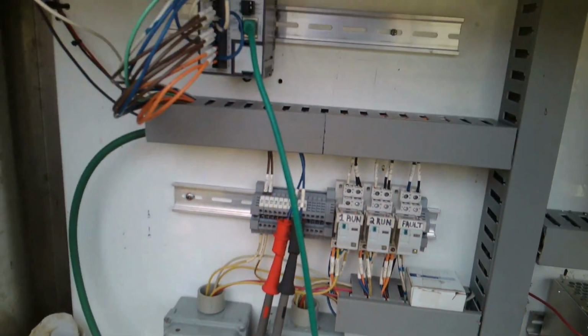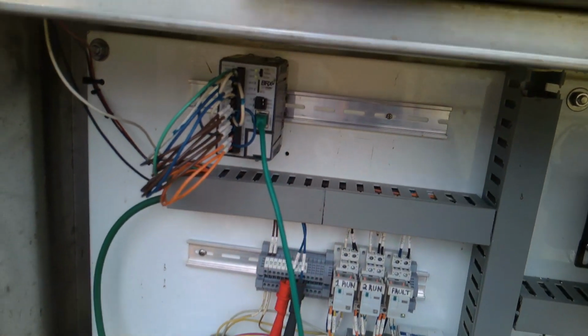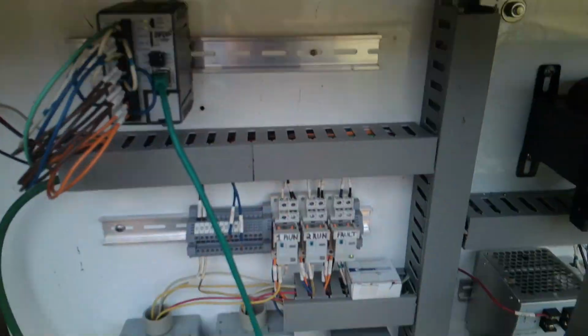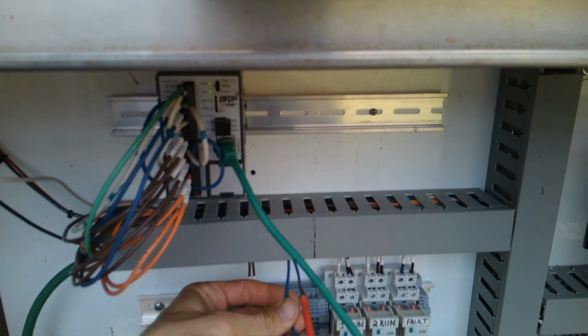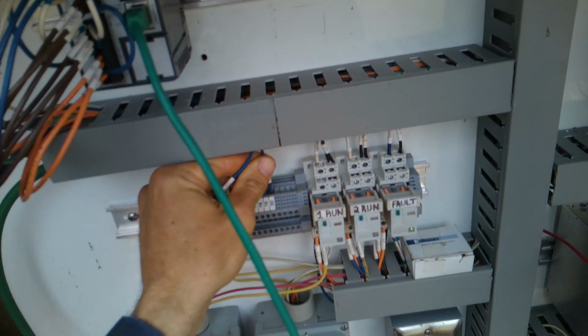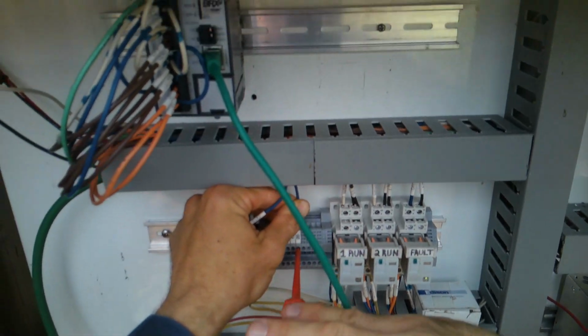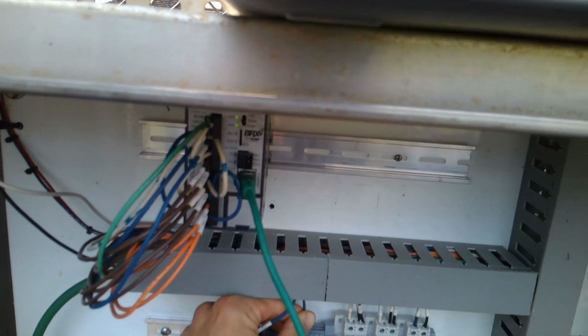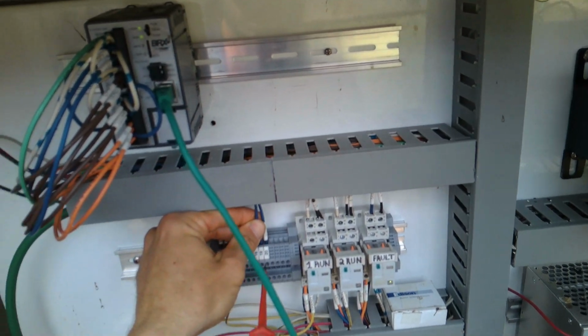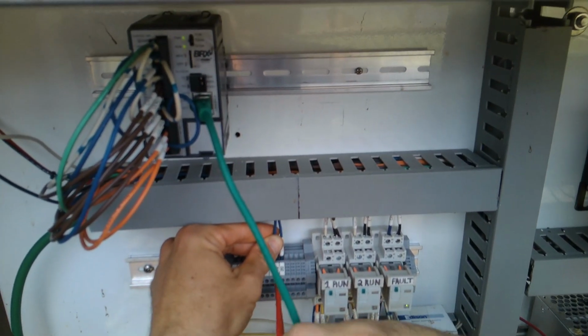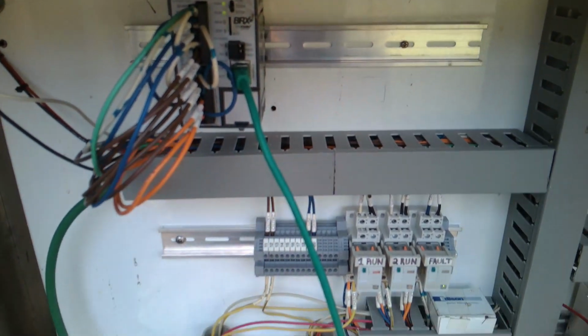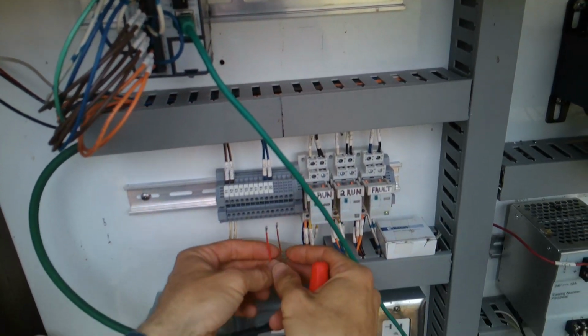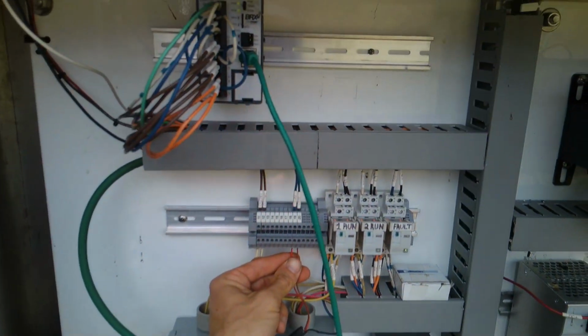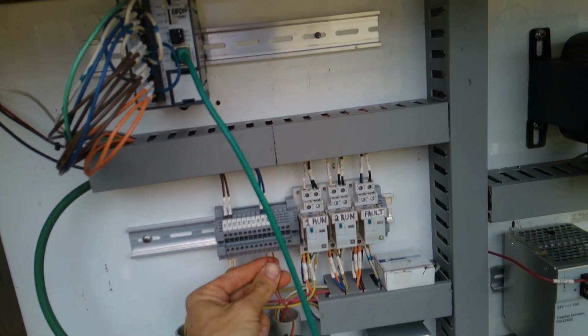Fortunately, this sump has a backup float mode, so we can leave it in backup float mode, and we can tell the operator that they need a new level transducer. Going to tuck those in like so. Yeah, look at it go. That transducer's toast. Tuck it in like so.